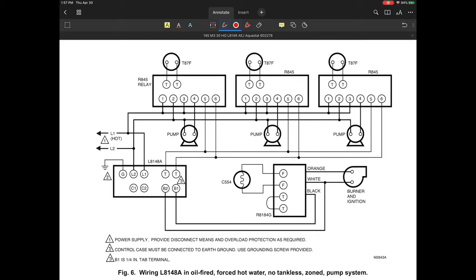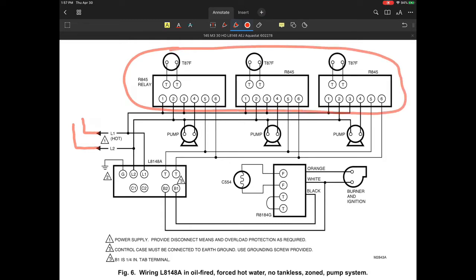All right, so what I wanted to show you is on this figure 6, what they're doing is they're showing me an oil-fired boiler system with 3 zone pumps. And how they're doing this is, in this particular application, this is one way to do it. My preference would certainly be to use a zoning board, maybe a 3-zone system, where it would integrate all of these into one. That would be my preference. But in this case, they're not showing that. So let's take a look at this.